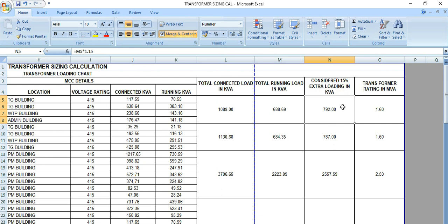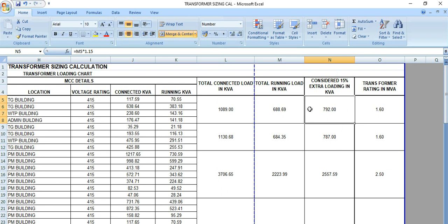Here we have considered 15 percent margin. Sometimes we consider only 10 percent depending on the situation. If it's a greenfield project, definitely will go for a higher side margin, let's say 20 percent margin. Sometimes we consider 25 percent margins in some of the real-time projects. Here we have considered 15 percent margin, extra loading for this transformer, which is coming almost 800 kVA.